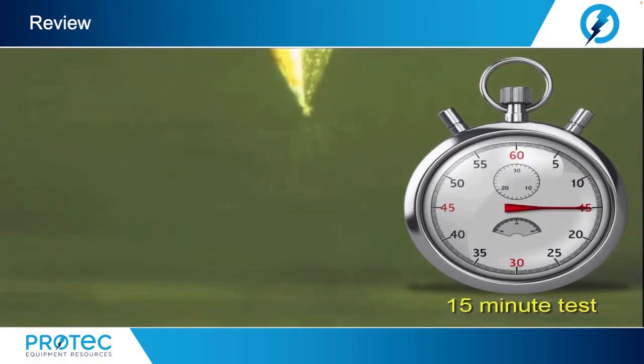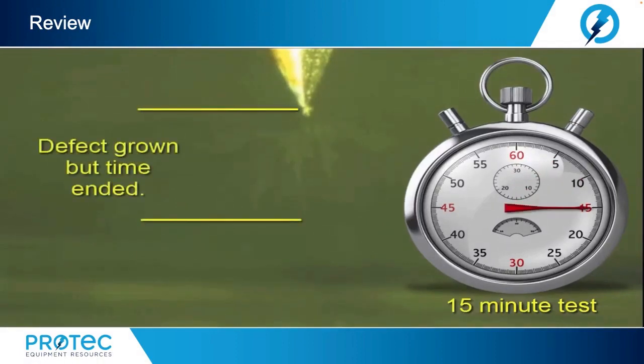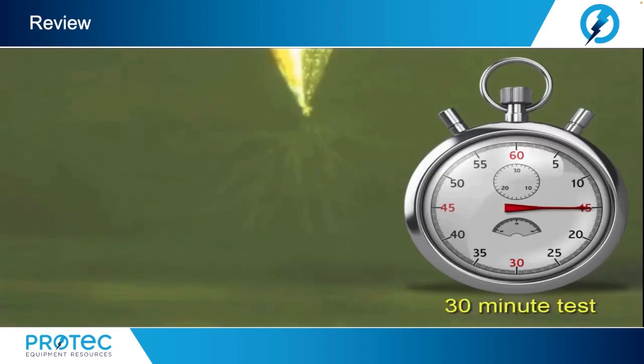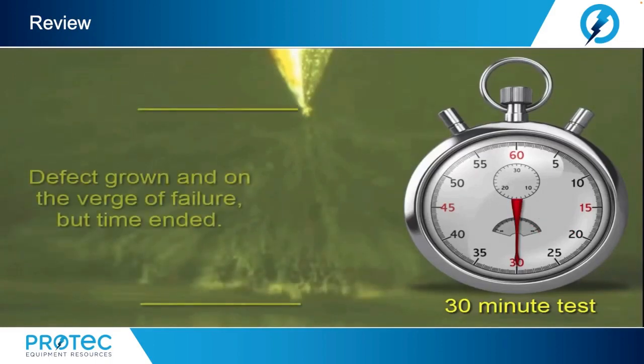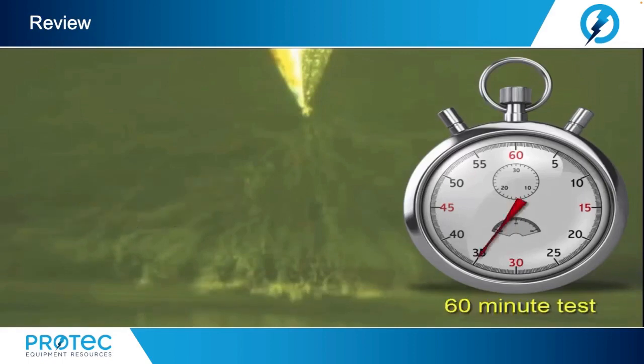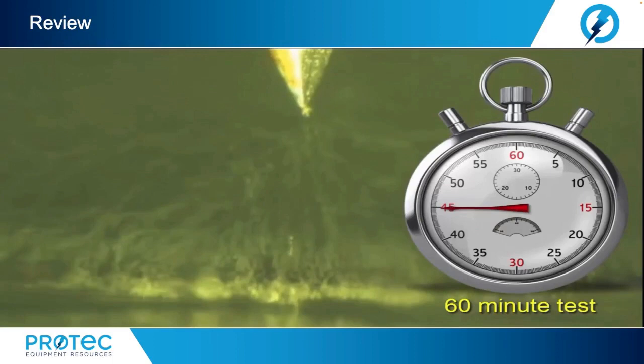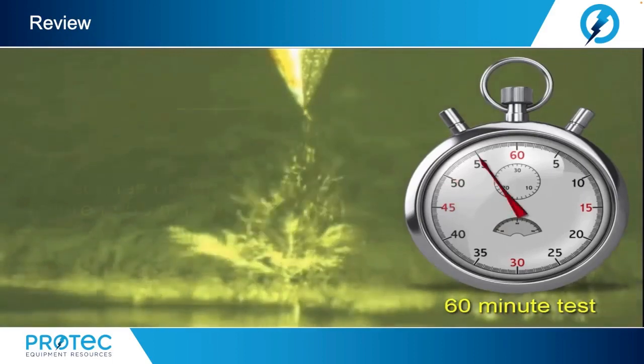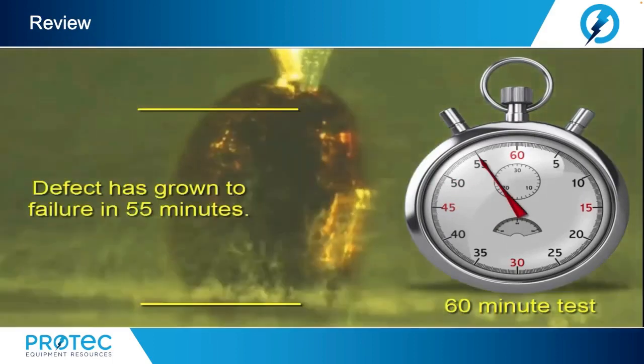For a fault to happen, the cable system must have a defect in the insulation or in the accessories. Also, according to the IEEE 400.2 standard for acceptance testing of cables ranging from 5 kV up to 35 kV, cables which are tested between 2 times U0 and 3 times U0 phase to ground, 68% of the failures occur within 12 minutes of testing, 89% within 30 minutes of testing, 95% after 45 minutes, and 100% after 1 hour of testing.